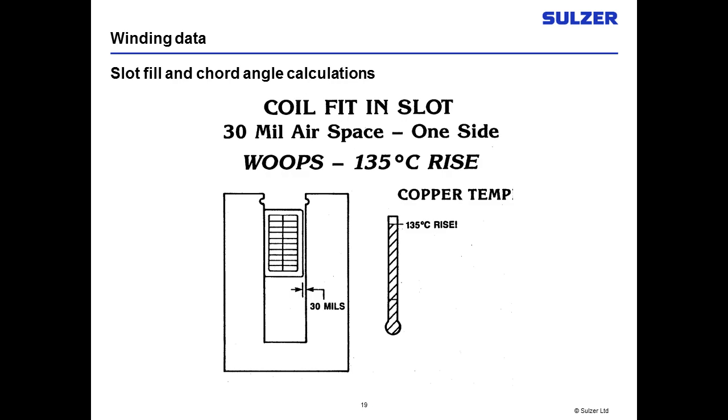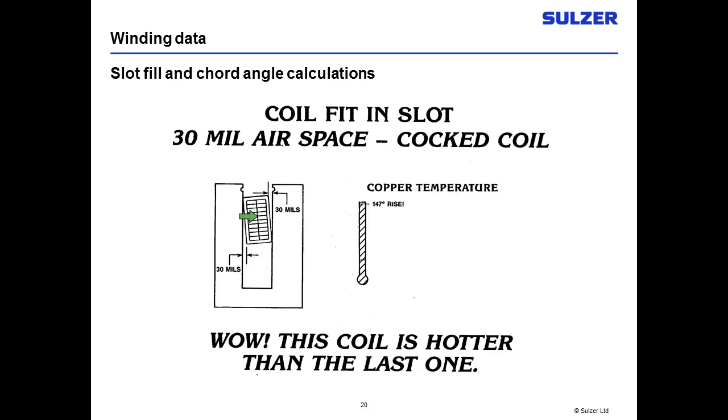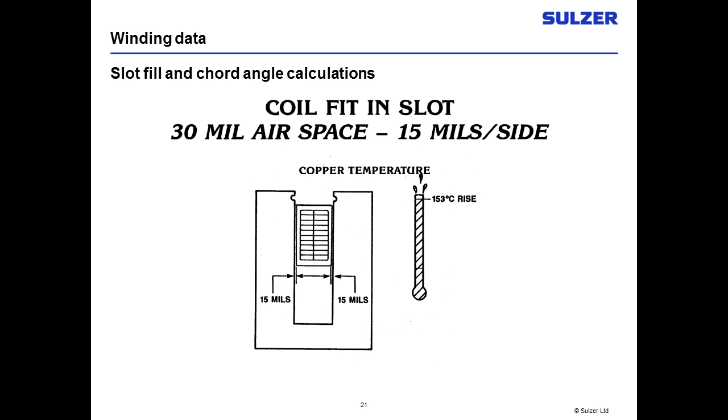On the second machine, they purposely made an undersized coil, leaving 30 thousandths air space to be filled with varnish. Same voltage and load — they had a 135 degree C increase in temperature. The third was made with coils tilted in the slot, not fitting straight, leaving 30 thousandths on each side — and they had 147 degrees rise. The fourth coil was made undersized with air space on either side — air is not a good heat transfer — resulting in 153 degrees centigrade rise over the original design. So you want your coil to fit the slot, which is especially important on higher voltage machines, 6,600 volts and above.